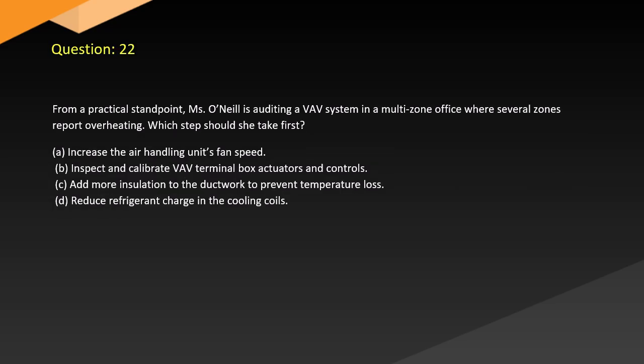Question 22. From a practical standpoint, O'Neill is auditing a VAV system in a multi-zone office where several zones report overheating. Which step should she take first? A. Increase the air handling unit's fan speed. B. Inspect and calibrate VAV terminal box actuators and controls. C. Add more insulation to the ductwork to prevent temperature loss. D. Reduce refrigerant charge in the cooling coils.